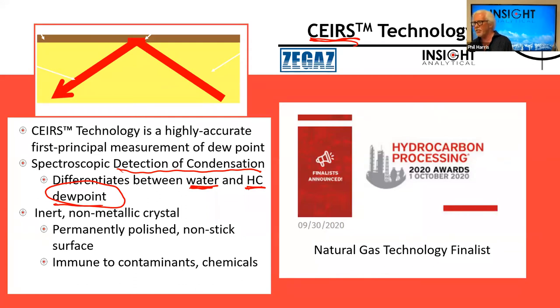No moving parts. Sohrab will probably answer better, but we typically see numbers in the 5 years for a lifetime of things like perhaps a thermoelectric chiller, that's a cooling part, 5 years plus. So it's quite low maintenance. It basically runs and runs. The maintenance is, like with many analyzers, often on the sample conditioning side. So in that part, it's how often do I have to change my filters out or coalescers out?